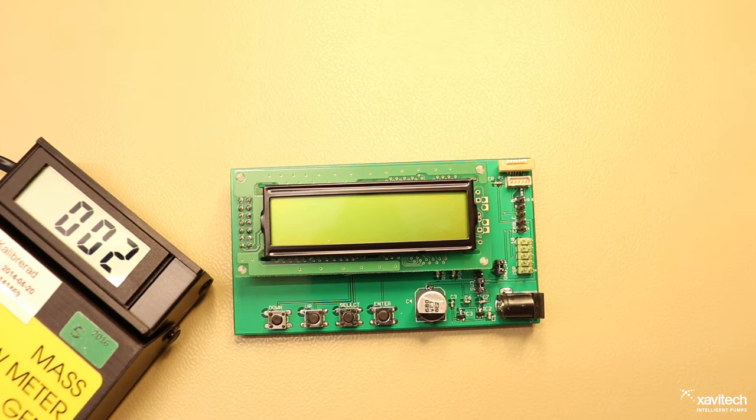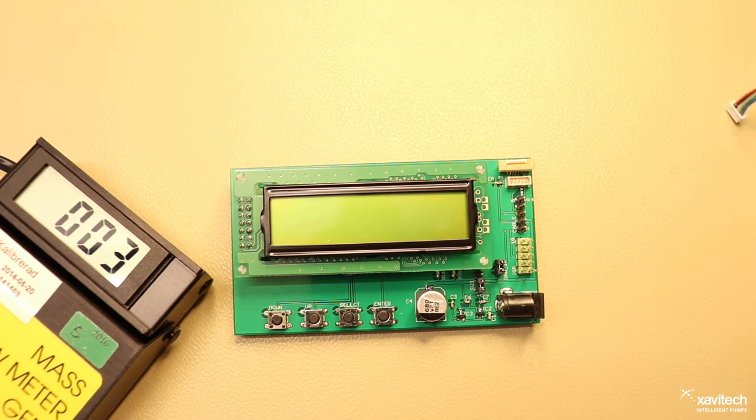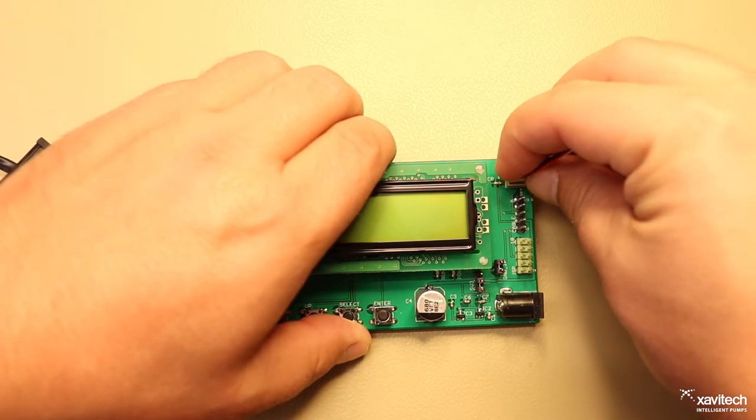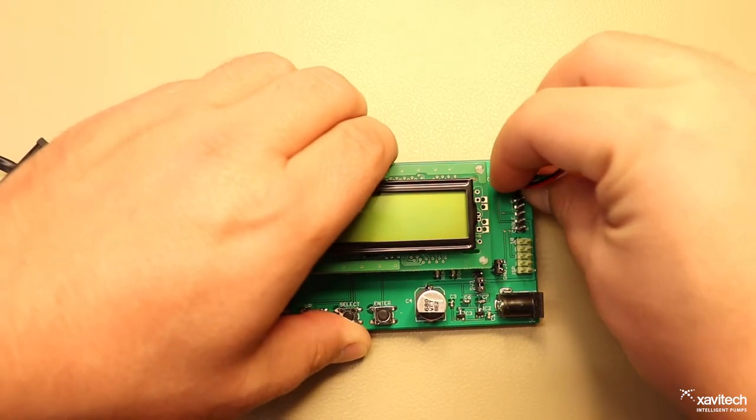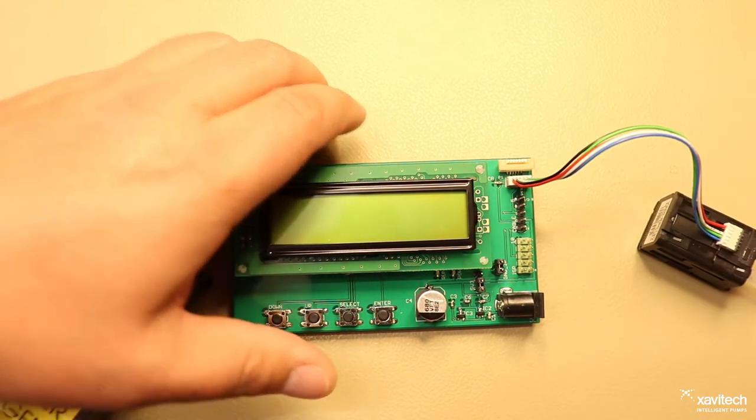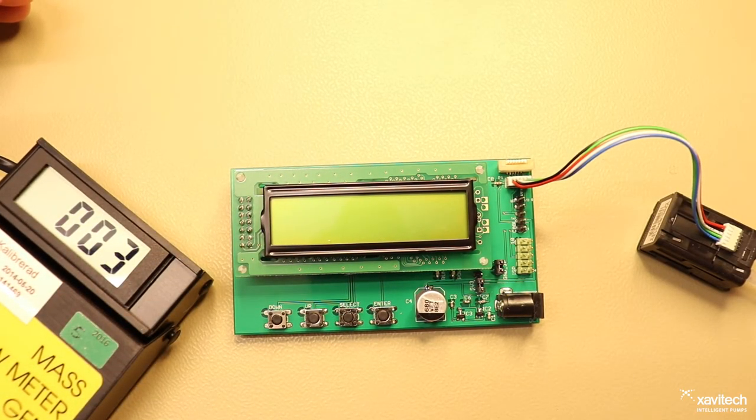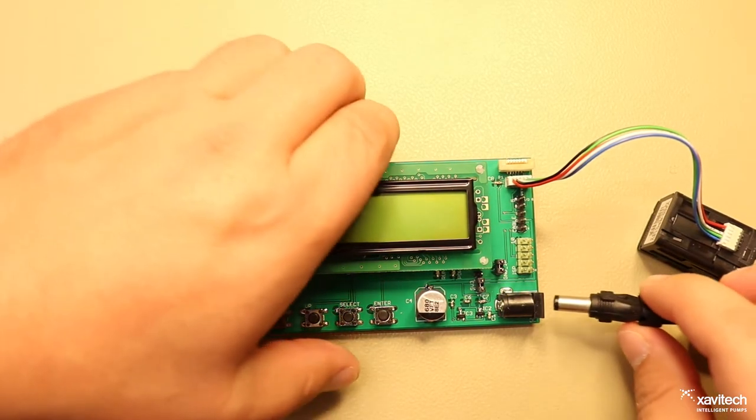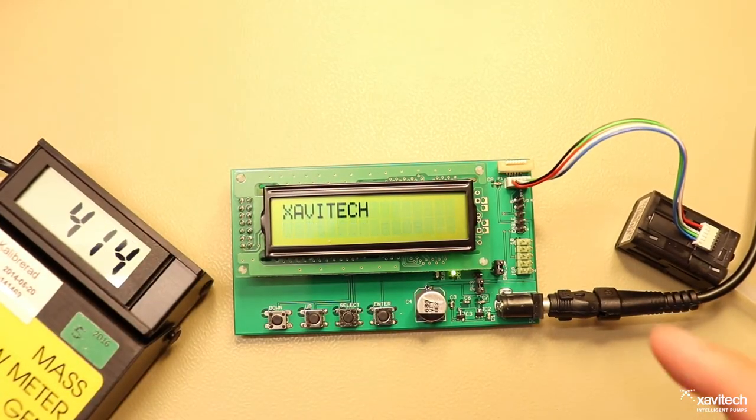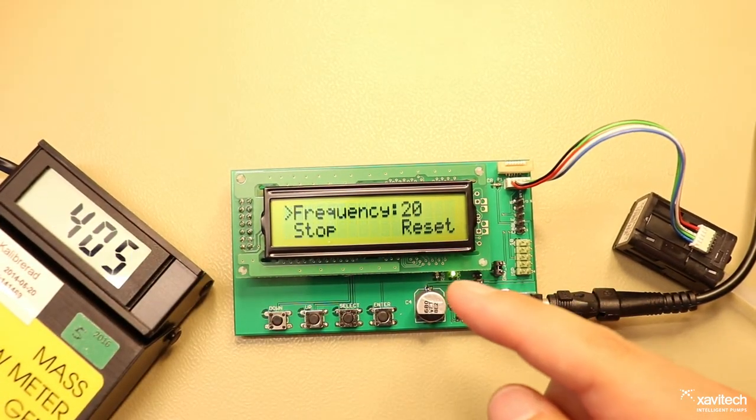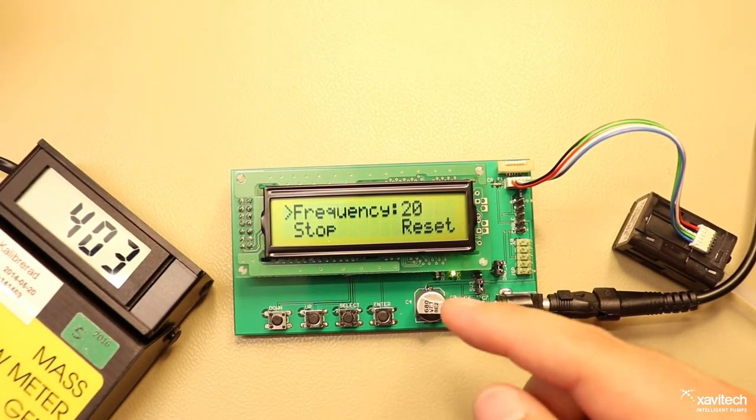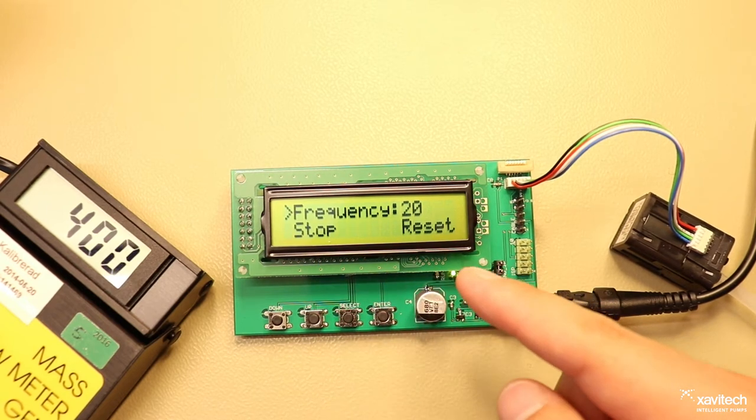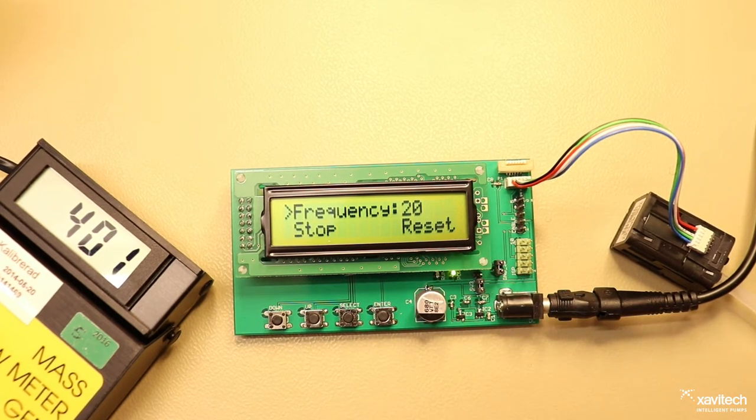To start using the FCU you first connect the pump and then you connect the provided power adapter to the barrel jack. The pump should start and you should see a welcome message and then this menu.